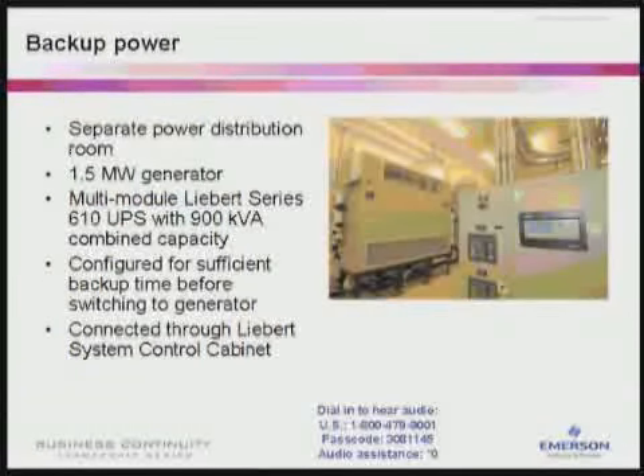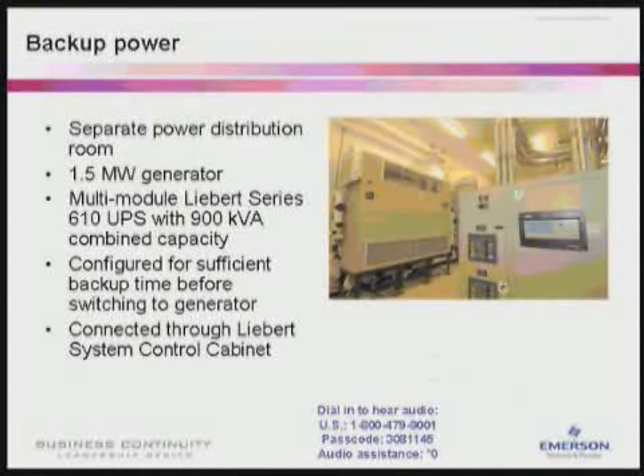Our backup power is a separate power distribution room where we operate that from. We also have a 1.5 megawatt generator, multi-module Liebert Series 610 UPSs with 900 kVA combined capacity, which will expand soon to 1350, configured for 15 minutes of backup time before switching to the generator, which we've tested, and it actually will last 15 minutes, although with our generator kicking in, it typically only is required to last a few seconds until our generator gets up to speed. And it's all connected through a Liebert system control cabinet.